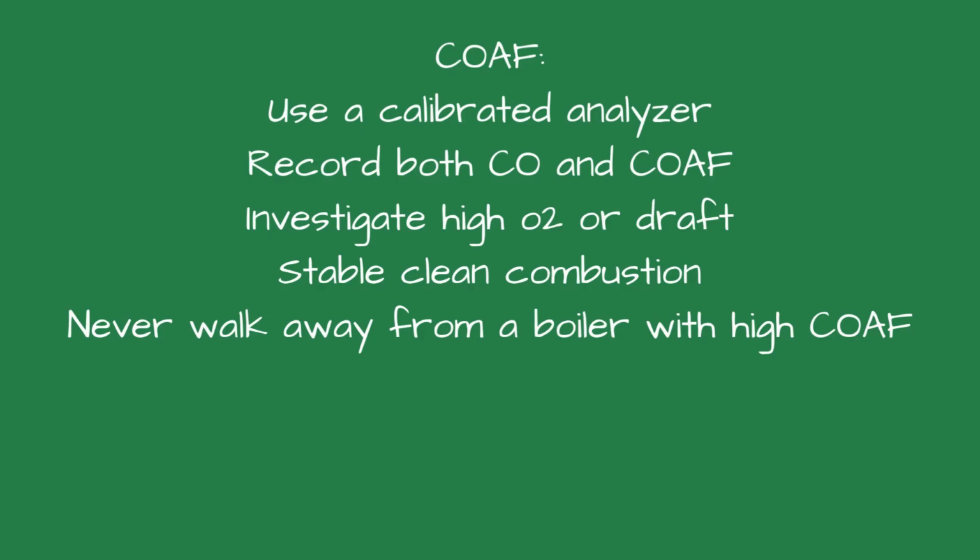Always test with a calibrated analyzer that supports CO air free calculations. Record both numbers, CO and CO air free, to see how excess air is influencing the combustion. Investigate high O2 or draft levels, which may be hiding problems. Adjust the burner for stable, clean combustion, not simply for low CO readings.